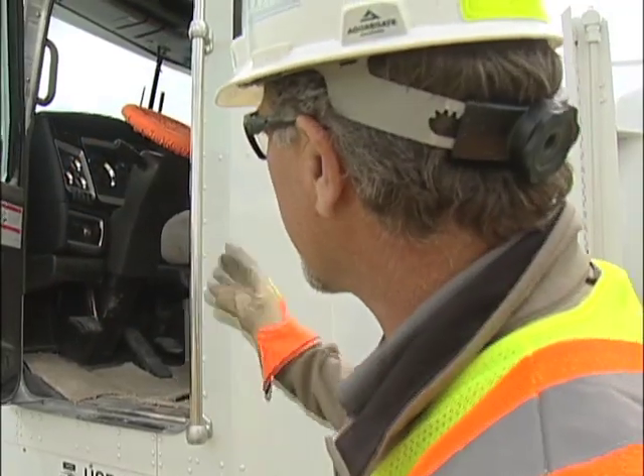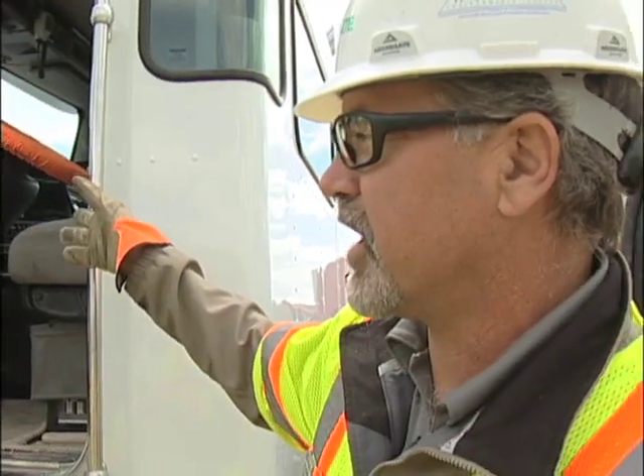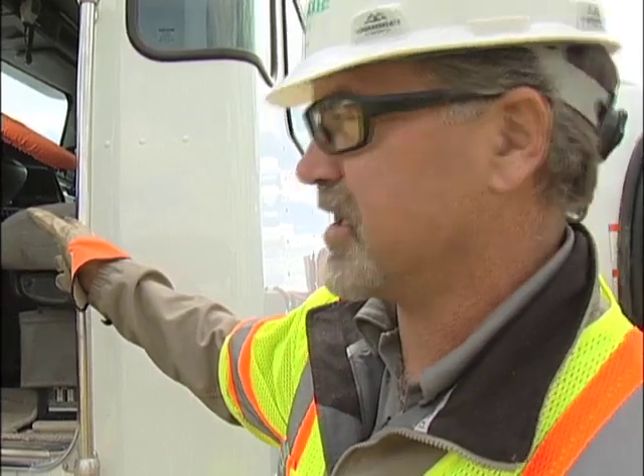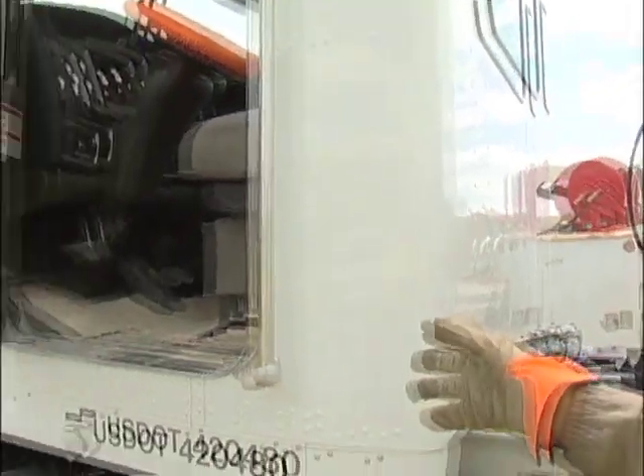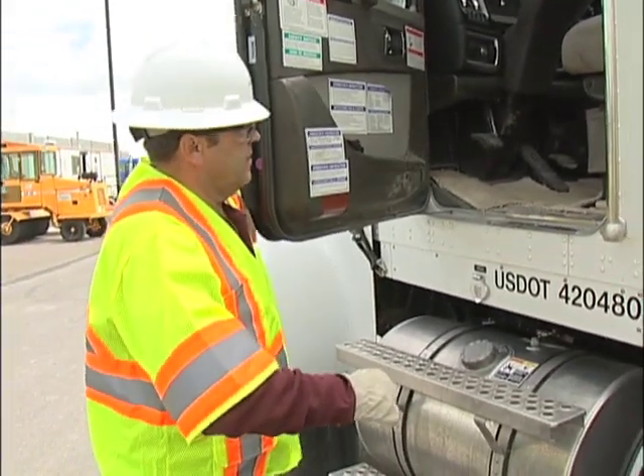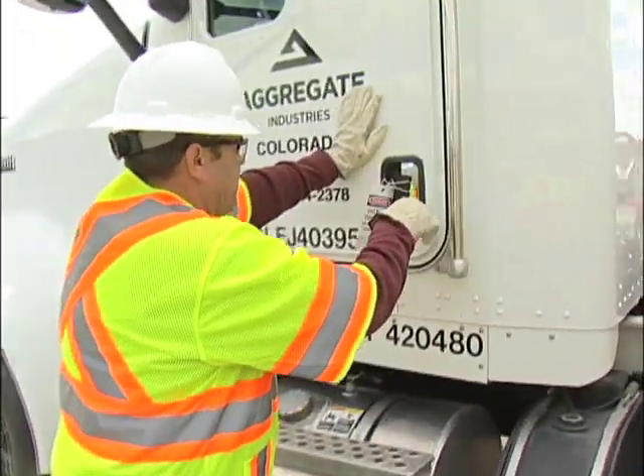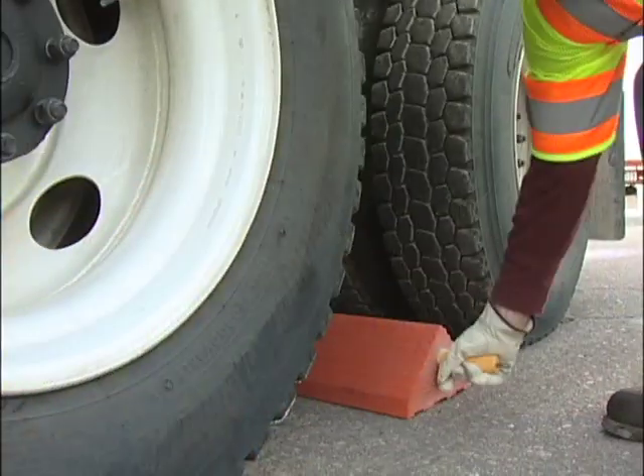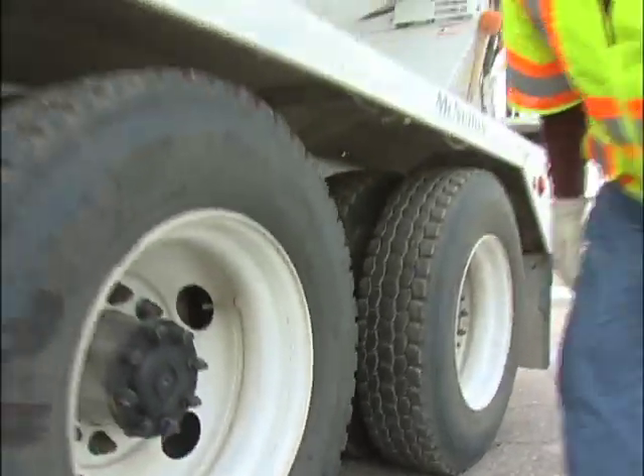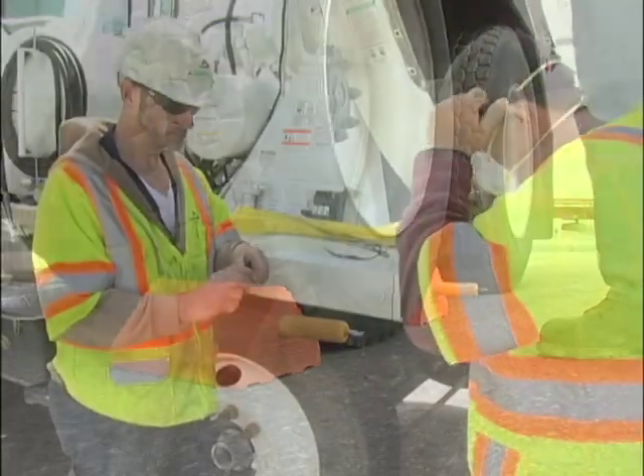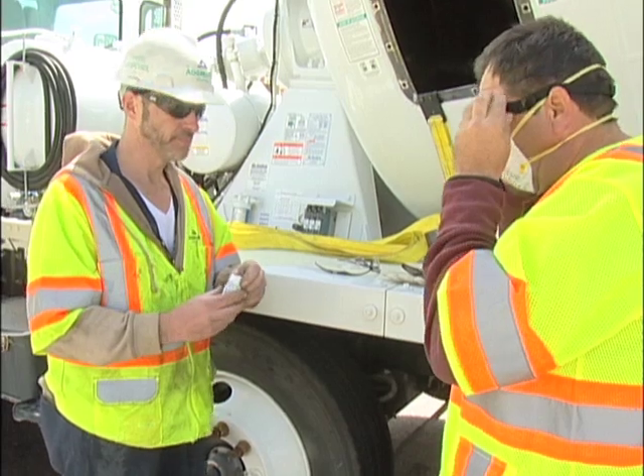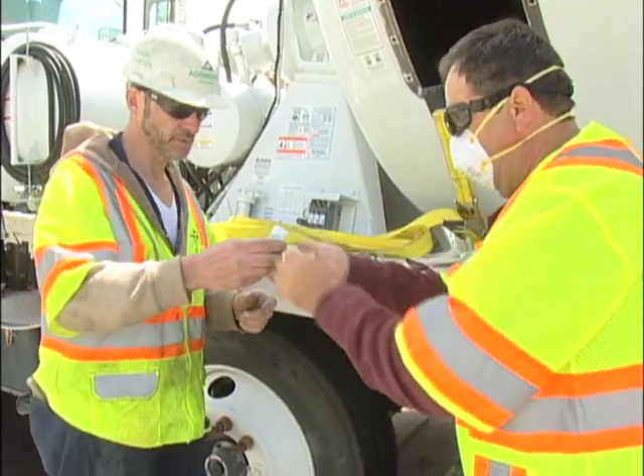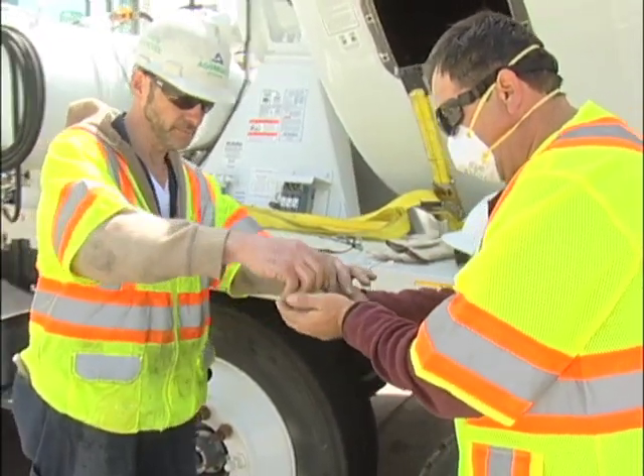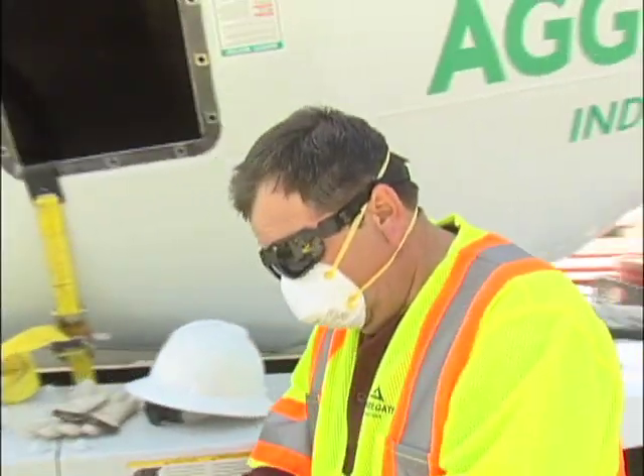Affected employees are workers whose job requires them to operate or use a machine or equipment on which servicing or maintenance is being performed under lockout, tagout, tryout. They could also be an authorized employee if they service or maintain the equipment. Training of employees is critical because these employees may be required to try and restart equipment under lockout, tagout, tryout if proper communication is not established.